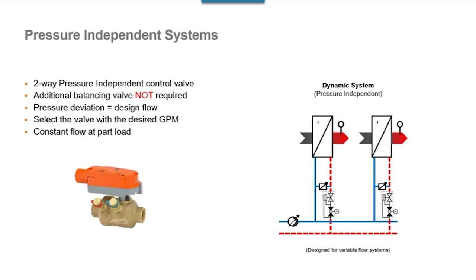Now, let me throw another question that I've heard a lot here. I've heard a lot that guys have said, well, gosh, this sounds really good, but I need more pressure drop across pressure independent valves. So I need more pump head. How am I saving energy if I need more pump head? Well, let's think about that a minute. Most pressure independent control valves, in fact, let me rephrase, all pressure independent control valves have a minimum and maximum differential pressure required across the valve, which you can measure in this valve in particular by tapping across the two ports.